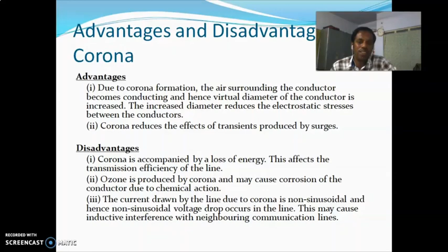So what are the methods to reduce the corona effect? The first one, by increasing the conductor size. By increasing the conductor size, the voltage at which corona occurs is raised and corona effects are considerably reduced. This is the reason we are using ACSR, aluminum conductor steel reinforced conductors, which have larger cross-section area, in the transmission lines, so that the corona will get reduced. You can see in the formula the visual corona voltage depends upon the radius of the conductor.